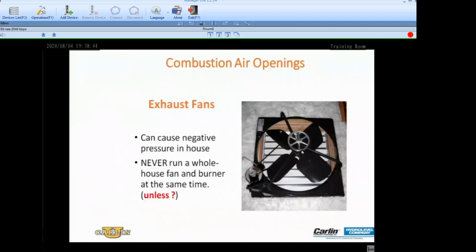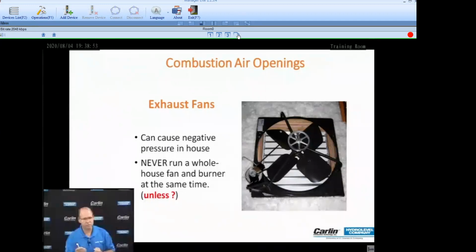How many of us have walked into a restaurant and when you go to open the front door to walk in, you need two hands to pull and you hear that gush of air go through as soon as the door is open? That's because the cook closed the door or the window in the kitchen and has the exhaust fan running, and they've set up negative pressure in the space.